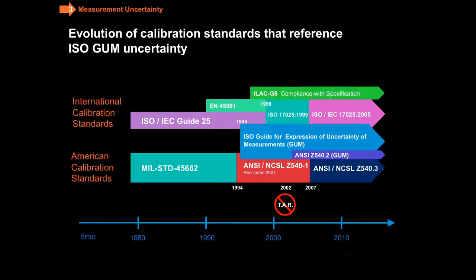And finally, ILAC G8, which is very important to many customers on how do you comply with specifications, makes specific references to the GUM, as does ILAC P14, which is a policy document that came out in 2010. When you use the accreditation symbol, you must have the GUM measurement uncertainty included in the report.